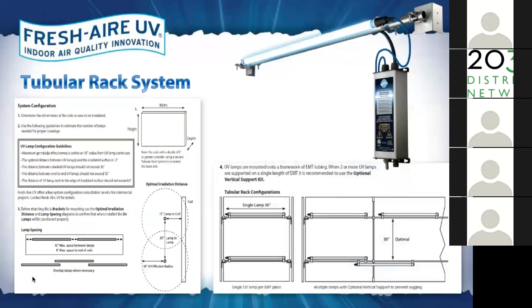Sizing the systems is actually really easy, but we can help you do it. We're simply spacing the lights out to a certain dimension to get maximum radiation into the coil itself. These are based on coil irradiation and irradiating a specific surface, but usually with just the lights sized for surface, it provides a log 2, log 3 reduction of COVID at the same time, because it's such a low dosage of UV.